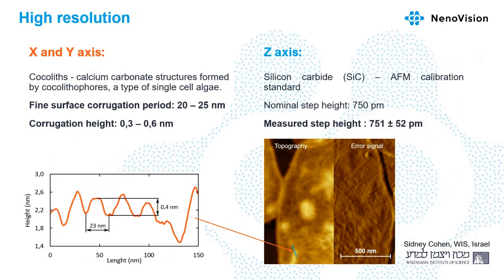LiteScope has very high resolution. In XY direction, for fine surfaces it's approximately 20-25 nanometers. And the limit in Z direction is less than a nanometer, as you can see here in the graph.